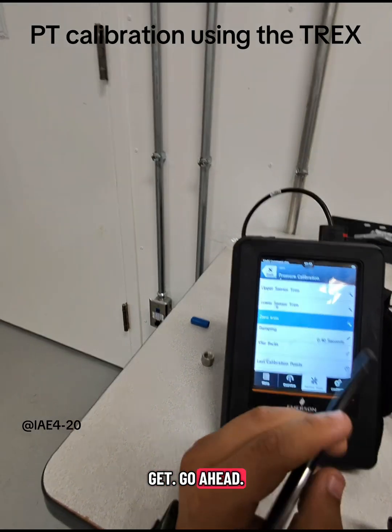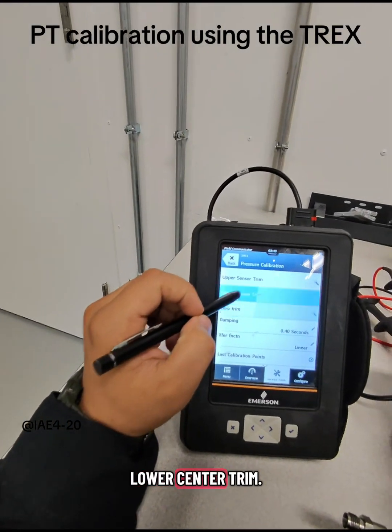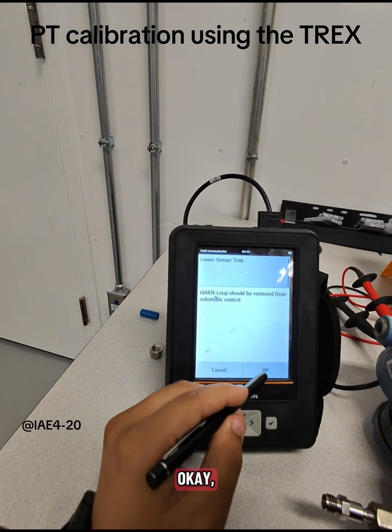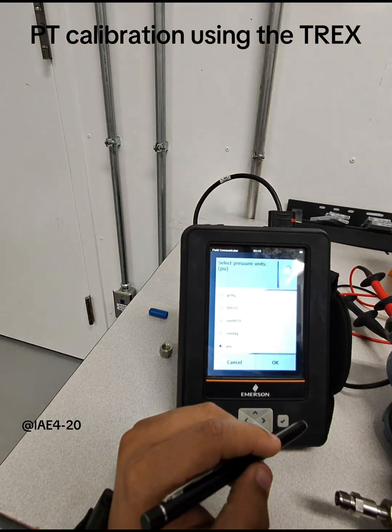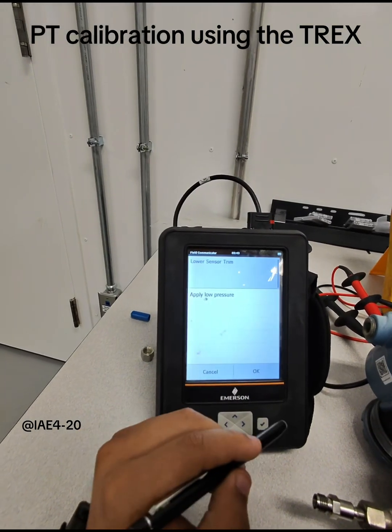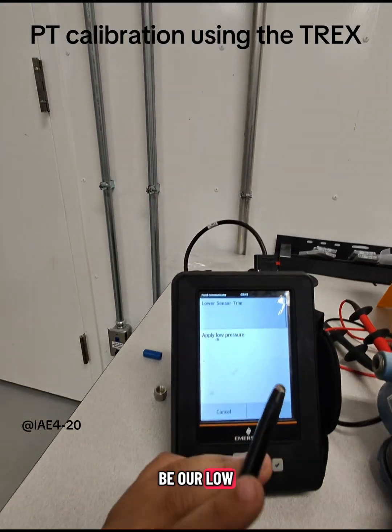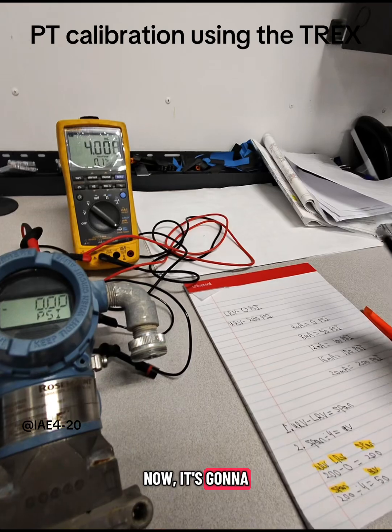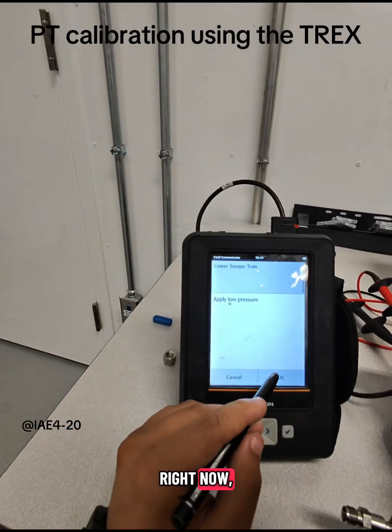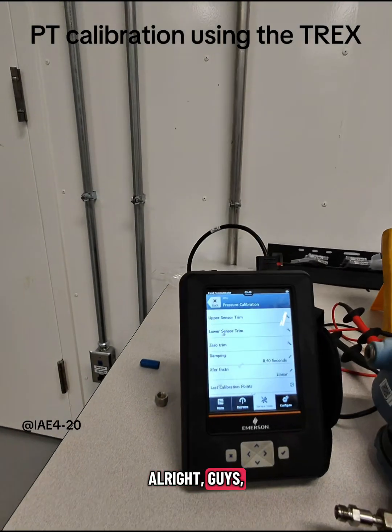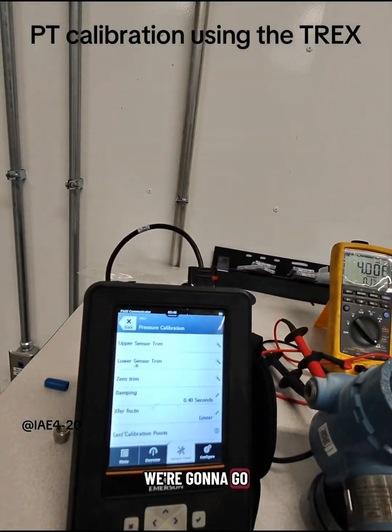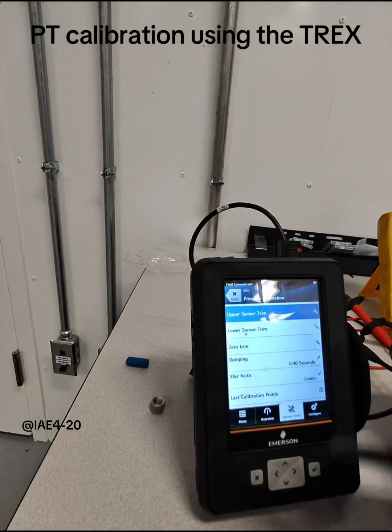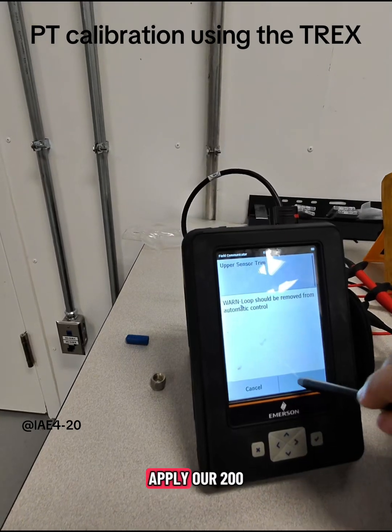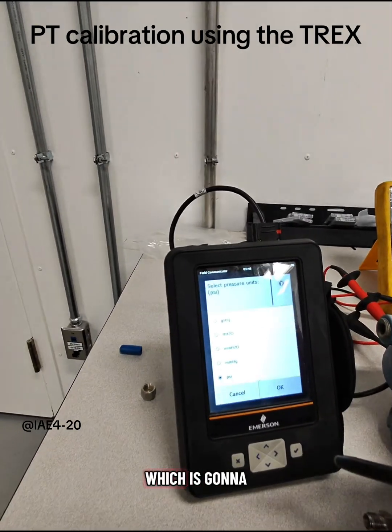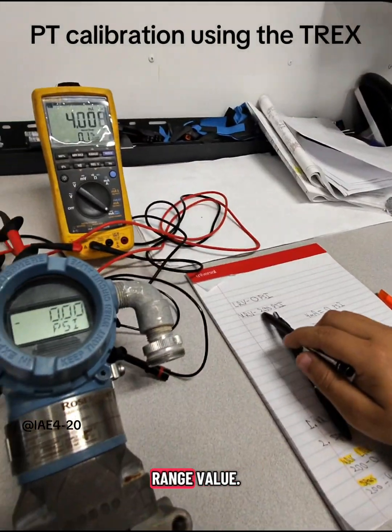So we're going to go ahead and go to lower sensor trim. Okay. We're going to go in psi. Apply low pressure. So this is going to be our low range value, which for right now is going to be 0. So we have 0 on it right now, so it's going to be okay. Alright guys, now that we did a lower sensor trim, we're going to go ahead and do an upper sensor trim. So we're going to go ahead and apply our 200 psi, which is going to be our upper range value, 200 psi. So now we have to apply it.